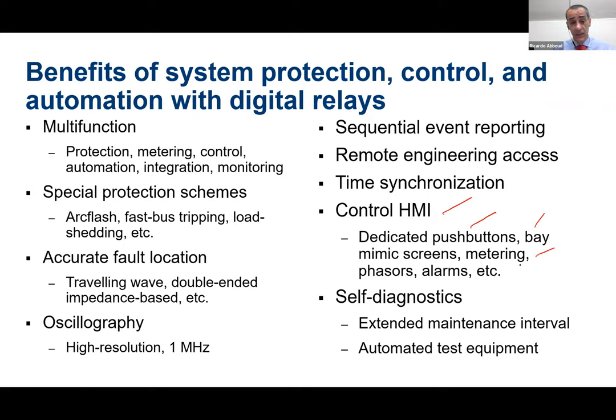So we can use that for SCADA metering. Of course, we are not going to use that for revenue metering, but we can use that for operation, for the SCADA. So you don't need separate meters for that function. And as already said, we have the self-test in the relay, so that can extend the maintenance interval. And also we can use some automated test devices. All of those benefits will translate into very simple things: we are going to reduce initial and operating costs applying the digital technology.